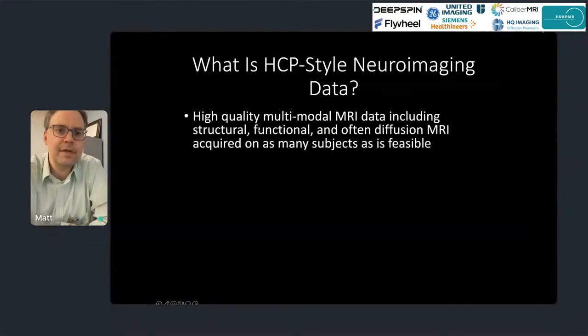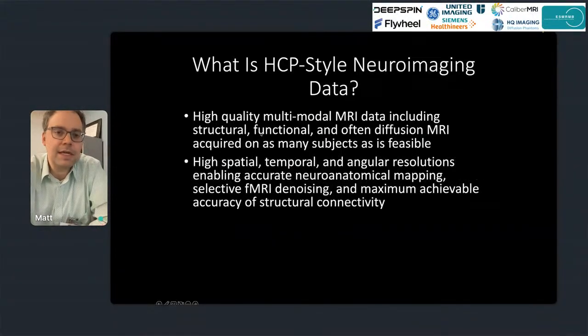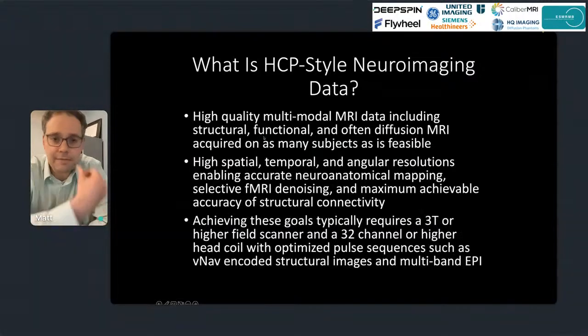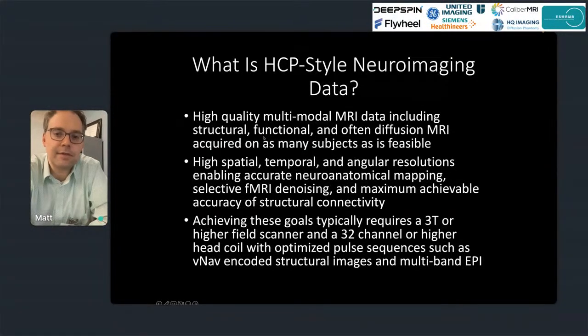HCP-style neuroimaging data refers to high-quality multimodal MRI data — including structural, functional, and often diffusion MRI — acquired on as many subjects as feasible. This uses high spatial, temporal, and angular resolutions, enabling accurate neuroanatomical mappings, selective fMRI denoising, and maximum achievable accuracy of structural connectivity. To achieve these goals requires at least a 3 Tesla or higher field strength scanner, a multi-channel head coil with at least 32 channels, and optimized pulse sequences such as multiband EPI or motion-corrected VNAV-corrected structural images.